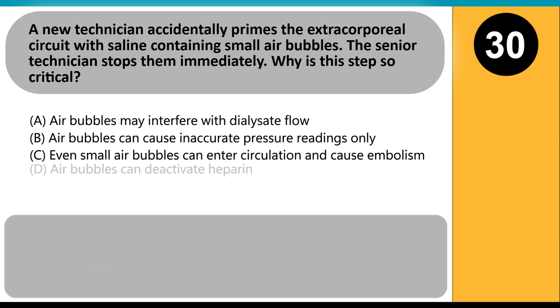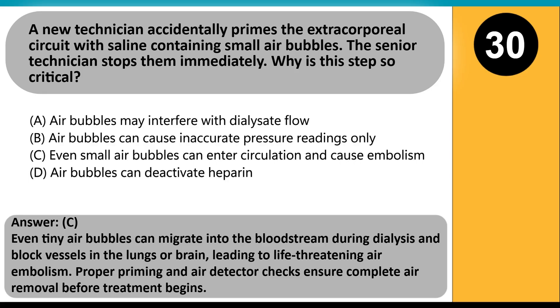A new technician accidentally primes the extracorporeal circuit with saline containing small air bubbles. The senior technician stops them immediately. Why is this step so critical? A. Air bubbles may interfere with dialysate flow. B. Air bubbles can cause inaccurate pressure readings only. C. Even small air bubbles can enter circulation and cause embolism. D. Air bubbles can deactivate heparin. Answer C. Even tiny air bubbles can migrate into the bloodstream during dialysis and block vessels in the lungs or brain, leading to life-threatening air embolism. Proper priming and air detector checks ensure complete air removal before treatment begins.